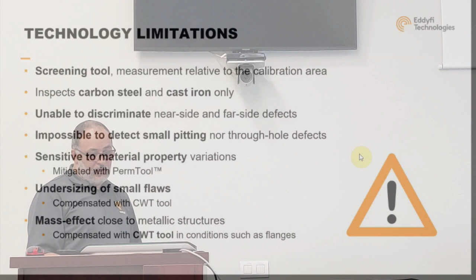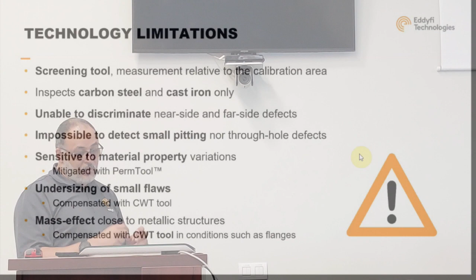Limited to carbon steel and cast iron, pulse eddy current technology doesn't allow you to know if the defect is internal or external. It just gives you the thickness measurement located, but doesn't tell you if it is near side or far side.